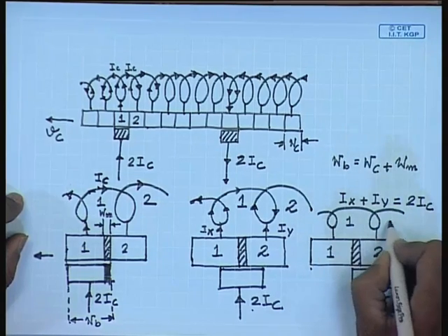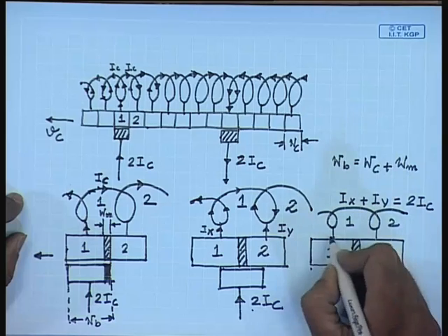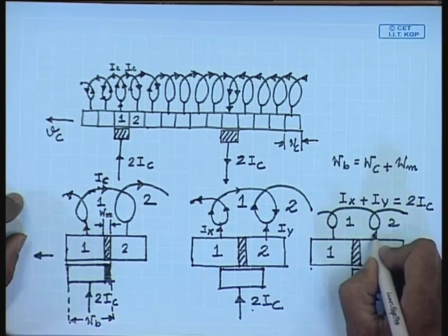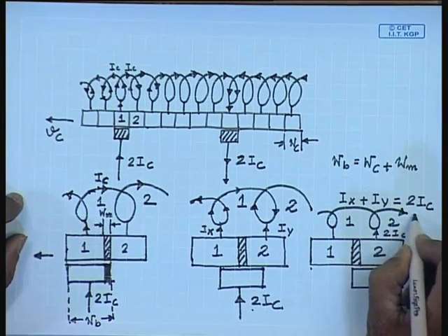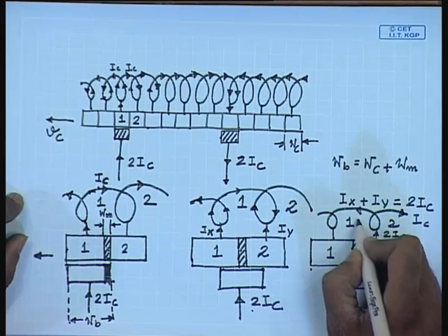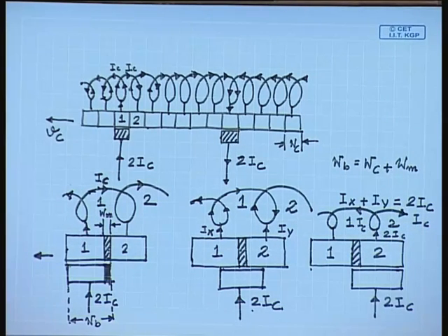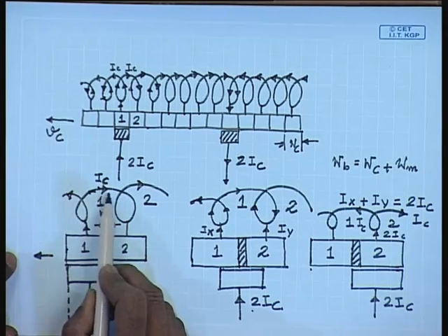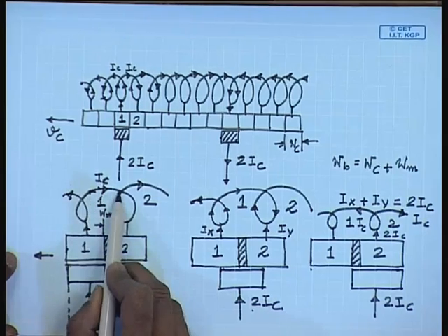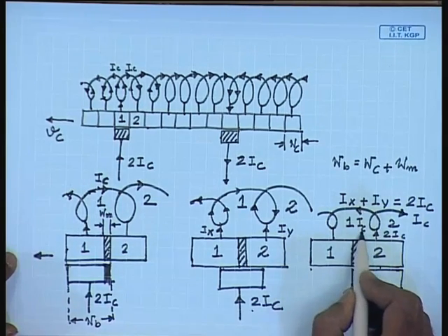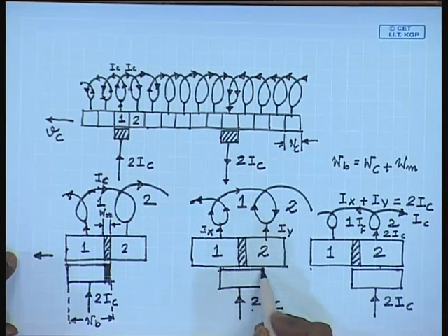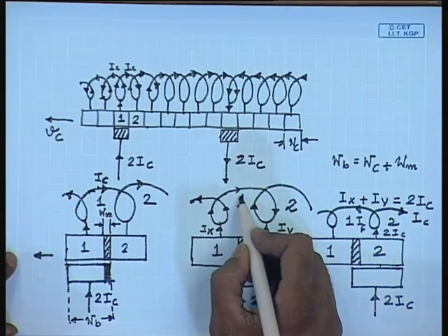This was coil 1, this is coil 2. So, once it has left, this current will now be 2 IC, this current will be IC, and this current will be IC. So, if we look at coil 1 current, in the beginning of the commutation, it was IC flowing from left to right. At the end of commutation, it still becomes IC, but from right to left.